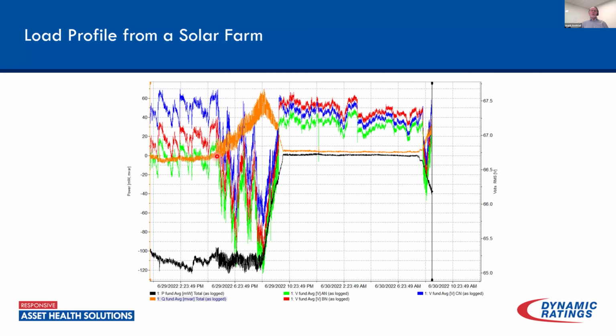What's interesting is how this shifts and how drastically it shifts when they're taking it offline, and here's when they're bringing it online. But when they're taking it offline, we can see that megavar output greatly increasing from basically 0 megavars, almost a unity power factor, to getting up here where we're producing 60 megavars. You can see our megawatt flow is pretty much staying the same. So when we see that, because we know VARs can have a significant impact on voltage, that's when we start seeing significant changes in our voltage profile here. And we're going to see that in some of the online monitoring data.